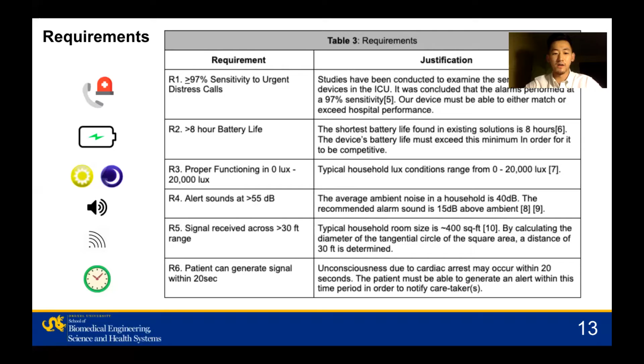Our verification process will include various testing procedures assessing the efficacy of some specific device components and overall sensitivity. Device sensitivity will be tested both before and after 8 hours of use, each time prompting patients to output distress signals at random time intervals. The sensitivity test will also be conducted at varying distances away from the patient to test the strength of the device's signal. Finally, our device's capability of outputting a sound at our proposed level of 55 decibels will be tested using the smartphone app Decibel X in conjunction with a calibrated external microphone. This traceability matrix denotes the need that is being met, verified, and any potential issues during the process.